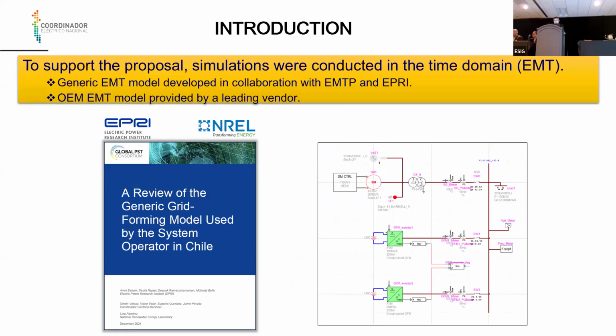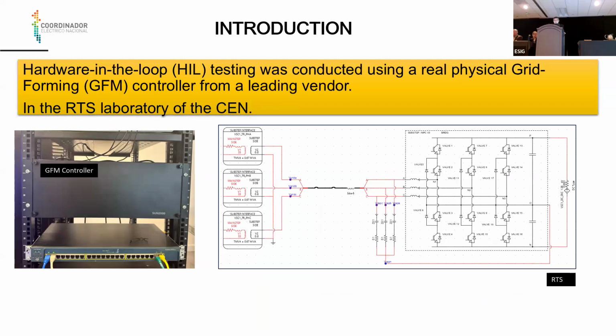simulations were conducted in the time domain with EMT tools. We used two models: a generic EMT model developed in collaboration with EMTP and EPRI, and the OEM EMT model provided by a leading vendor. The product of this collaboration was a document by EPRI, NREL, and us. Regarding the hardware-in-the-loop testing, that was really a control hardware-in-the-loop test, because it was conducted using a real physical grid forming controller from a leading vendor.